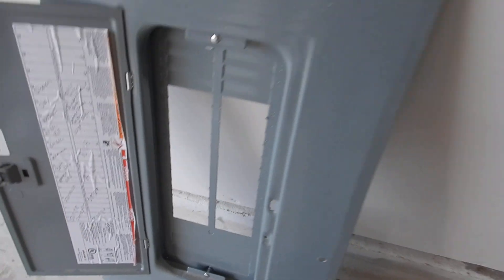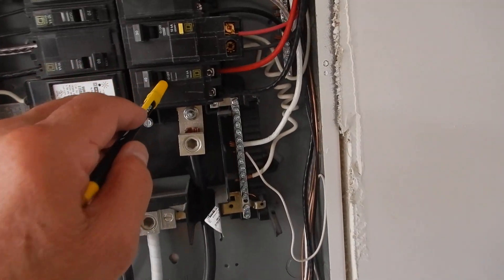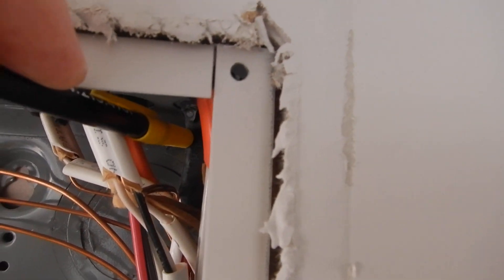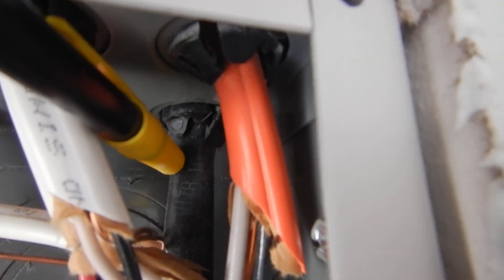Okay, this is your range. It's fused right for the range. These cables, they're number 10. They're number 10, supposed to be number 8. Eight's larger than 10. I'm going to hold it real steady so you can zoom in on that. It's supposed to be an 8.